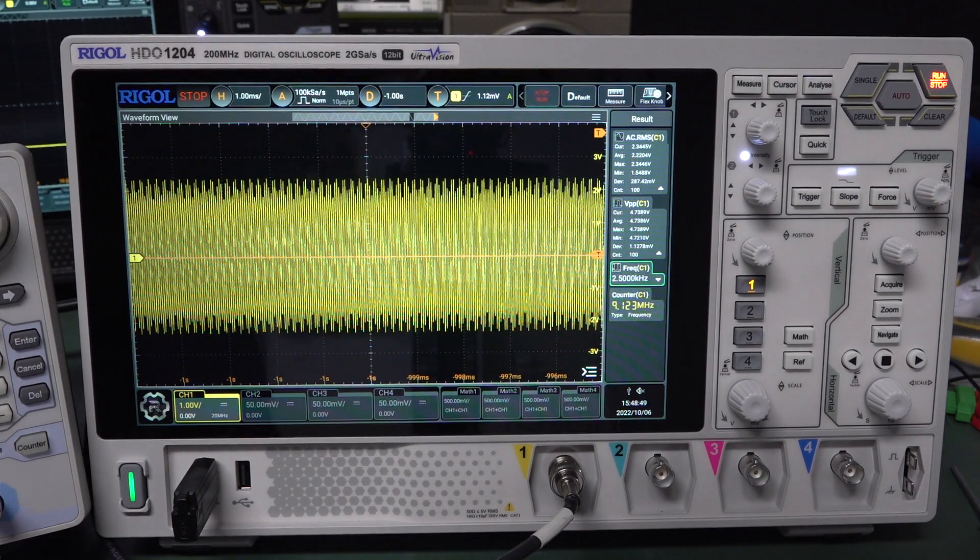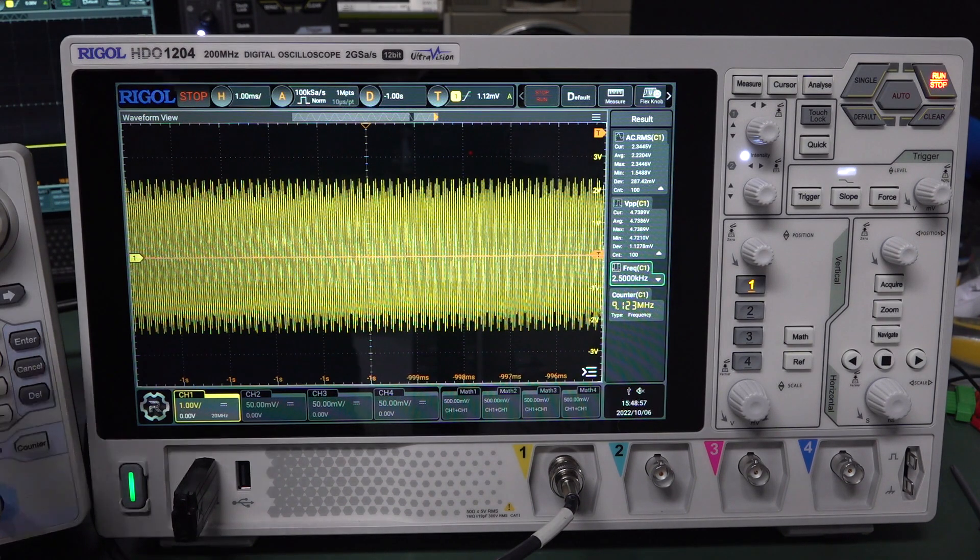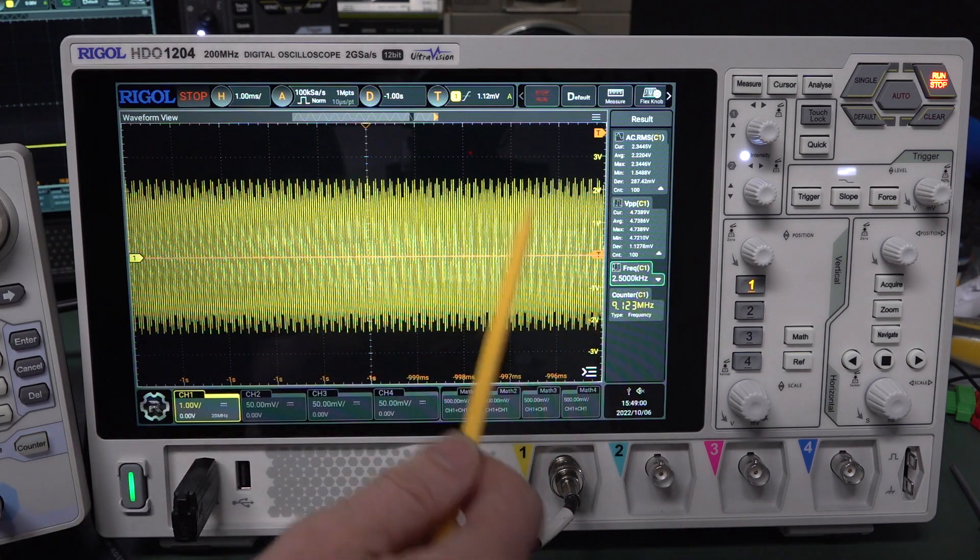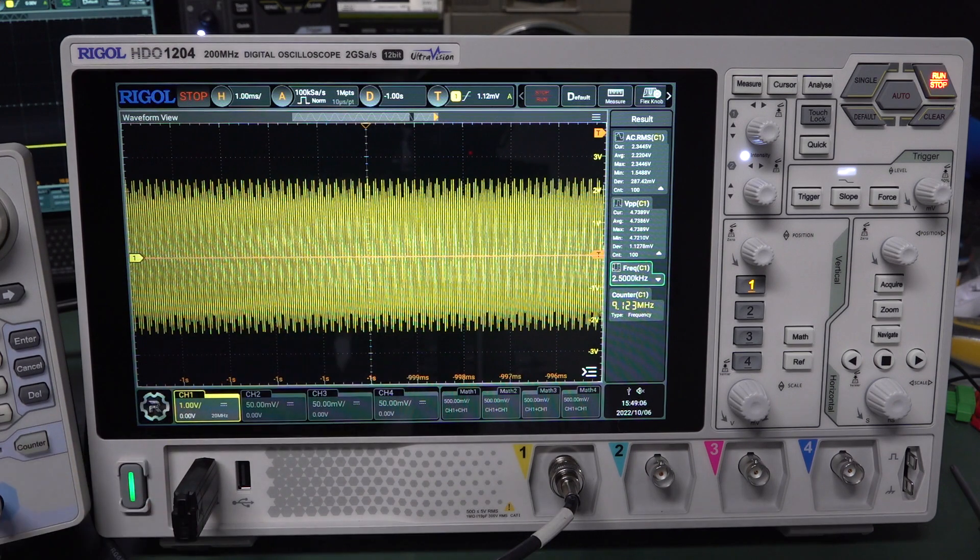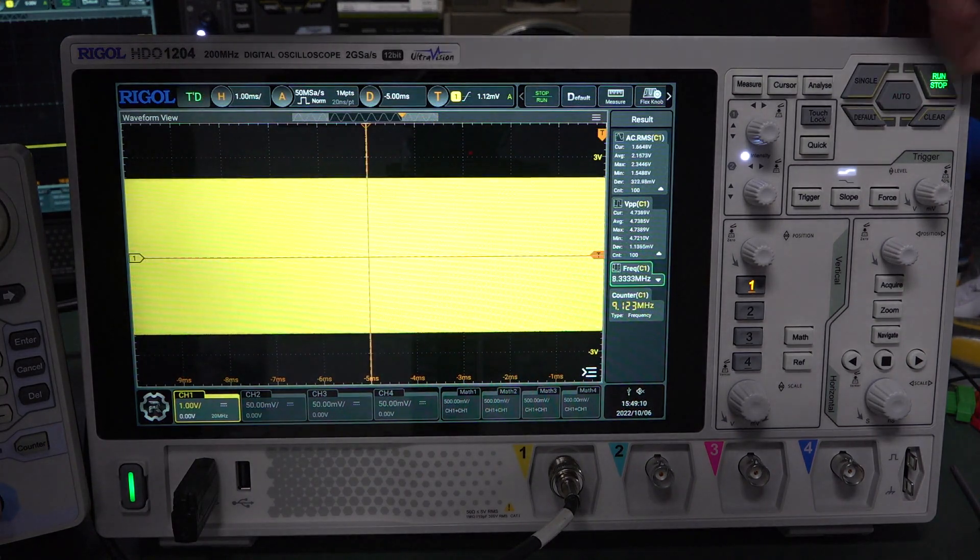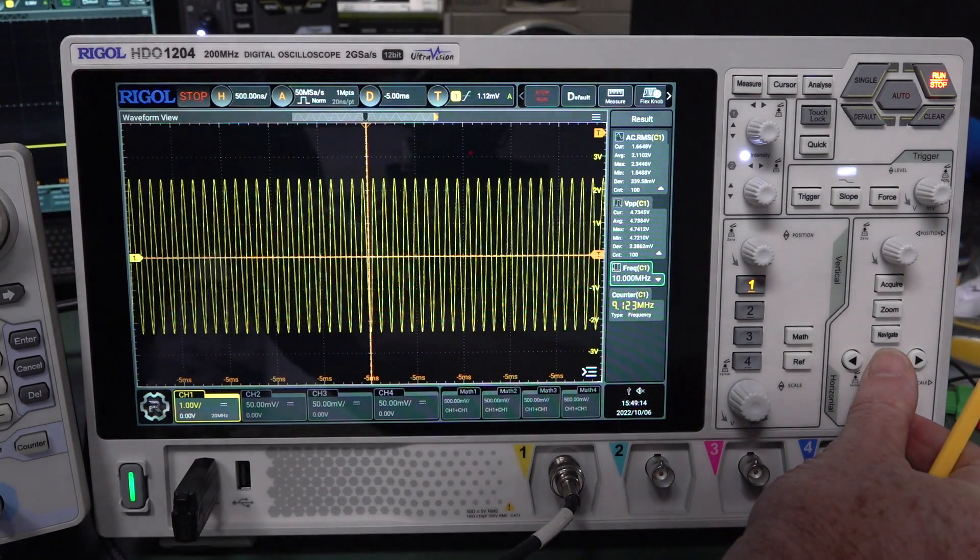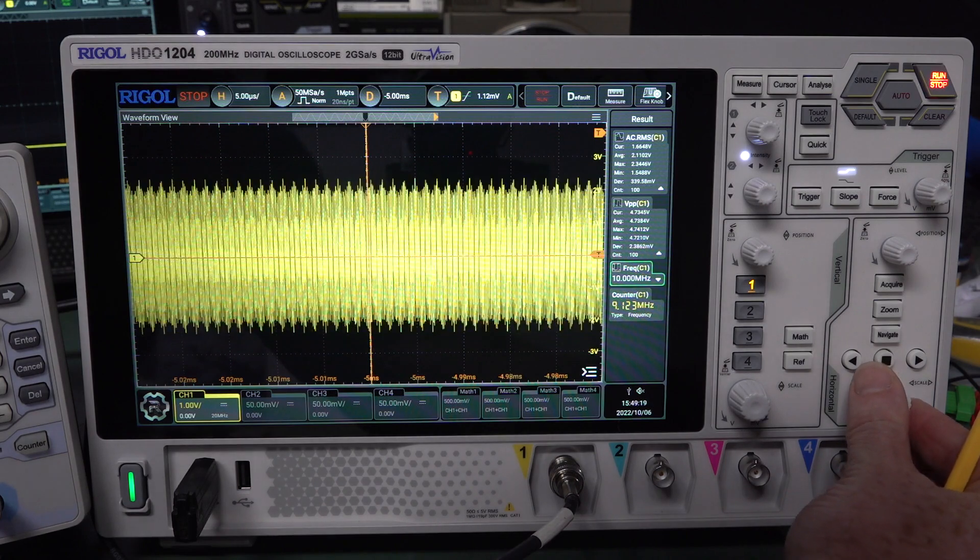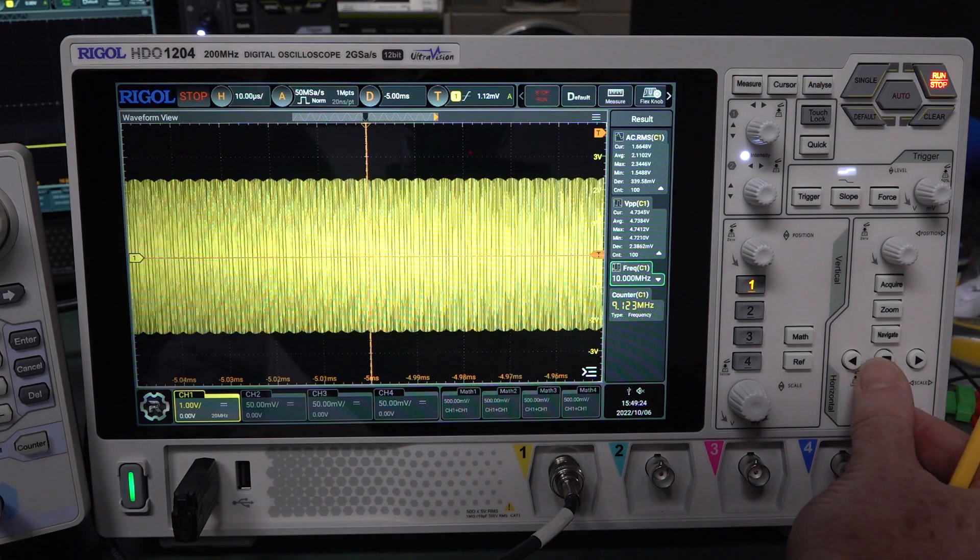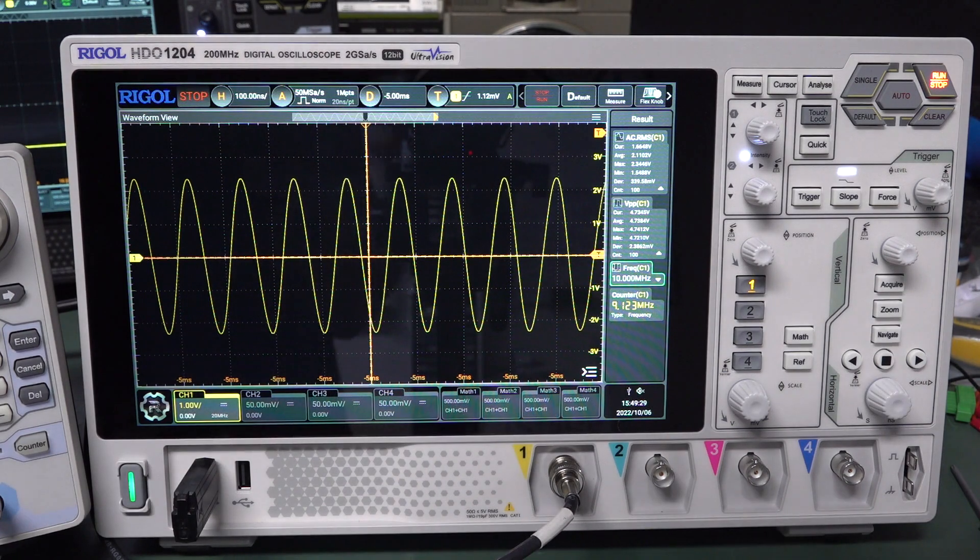But yes, it ultimately will... I would still call this aliasing. But how it implements itself on the screen in the hardware. You know, once again, the stopped display algorithm might be different to the real-time display algorithm as well. So, you know, and that looks to be sort of the case here. Because if we run that, right? Look. Right? And then if we stop it in there, because we're stopped at a different sample, it's going to be different again. There you go. Look at that. Wow! Look at that. One time-based difference between those. Funny business. Right? And every scope is going to do this differently. So yeah. But there's clearly no anti-aliasing filter in this scope. And I think most scopes don't have one.